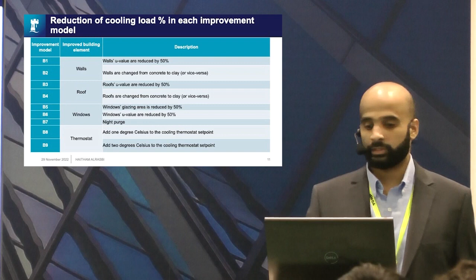So what we did here is 9 different simulations. For each simulation, I changed one element of the building. The first changes U-values to reduce by 50%. The second, B2, changes the walls from concrete to clay, and the same for the roof and the windows. B8 and B9 add 1 degree or 2 degrees Celsius to the thermostat set point. Now I'll show you the results.